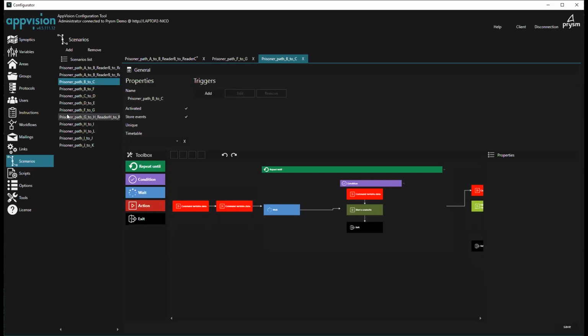By script, we can do that, because by script we can transfer an alarm to another user. But the alarm escalation severity is here to manage the display of this alarm to a different user profile, because you can filter a user profile on a specific severity level.